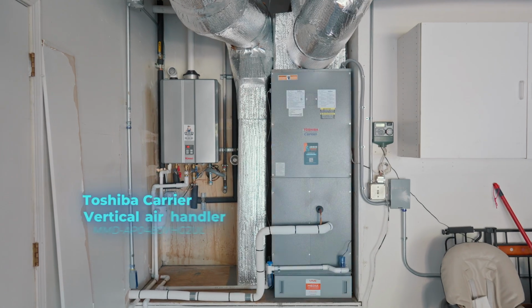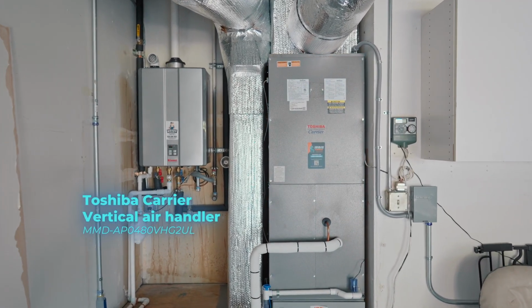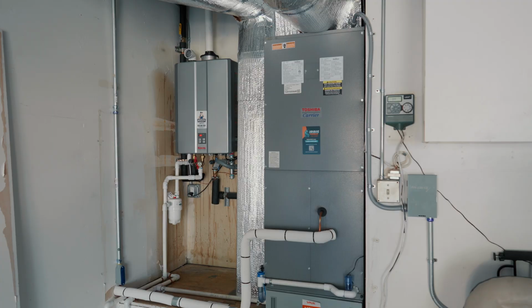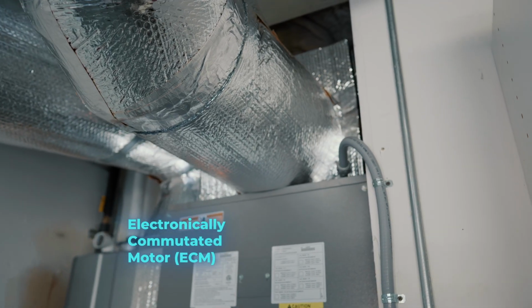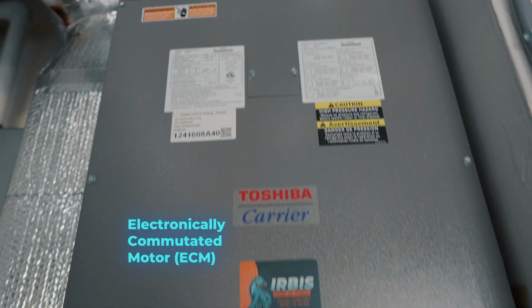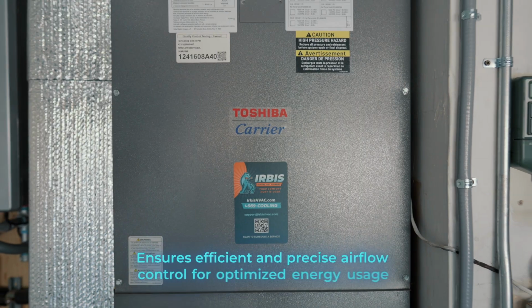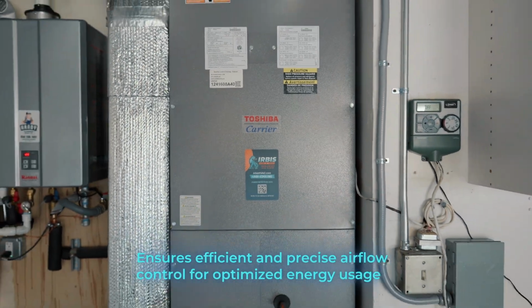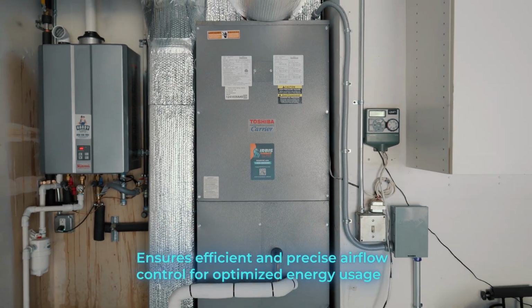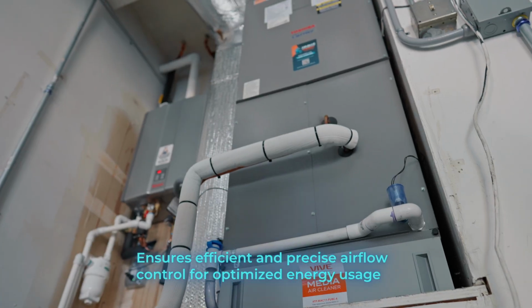So inside the garage, we installed the vertical air handler, also 4-ton in size. This air handler uses an ECM motor, which stands for electronically commutated motor. In simple terms, that means the fan motor is smart. It can slow down or speed up automatically to keep the temperature and airflow just right, while using much less electricity than a regular motor.